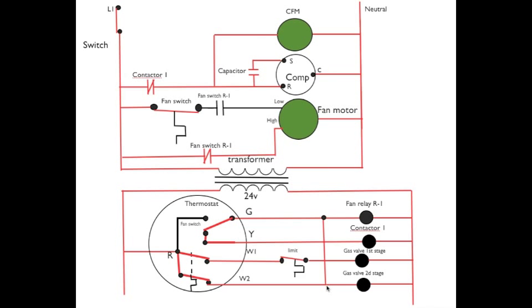Power is passing through this red wire up here. And while I'm at this, notice I did not put a dot here or a dot there. That's one of the ways a diagram can indicate that there is no connection there. There has to be a little ball or dot where it makes connection. Not all diagrams do this, but some do, so I'm using it here. Okay, the power would pass up through here and energize fan relay R1.